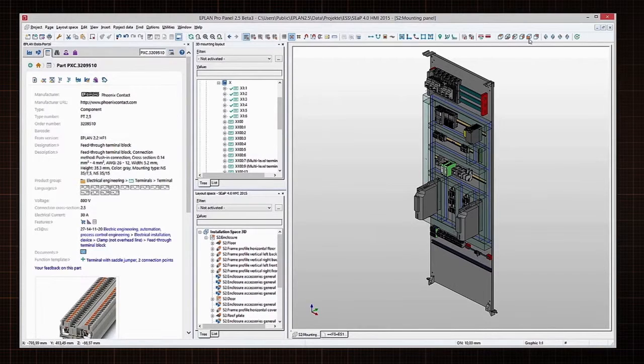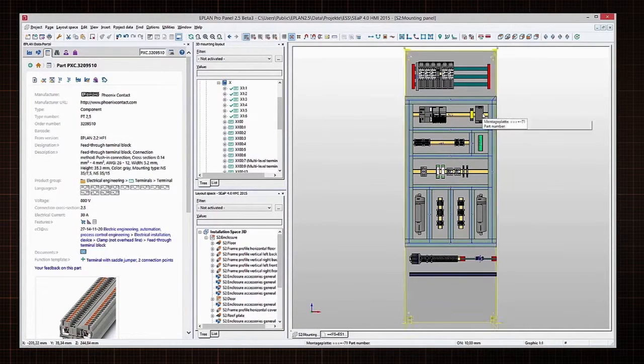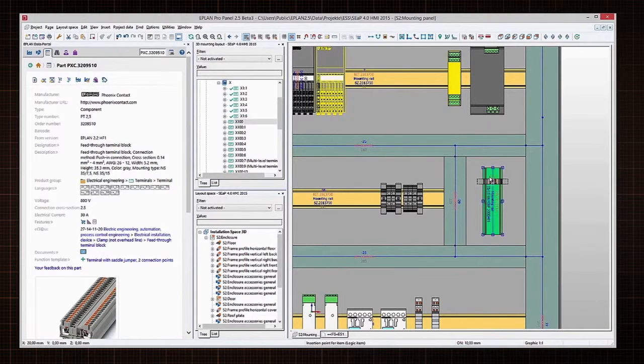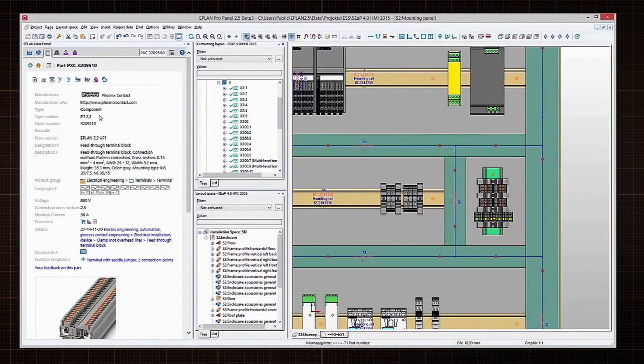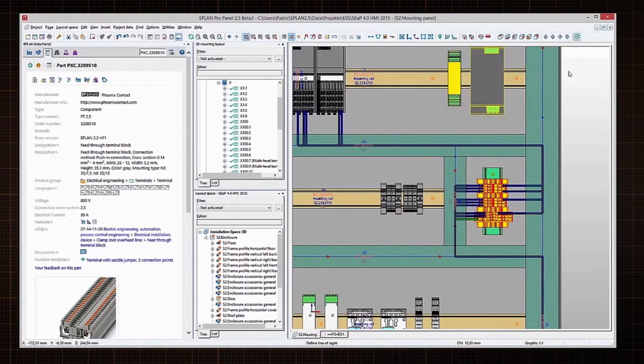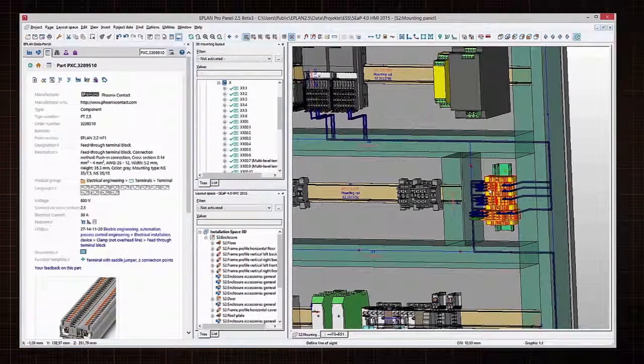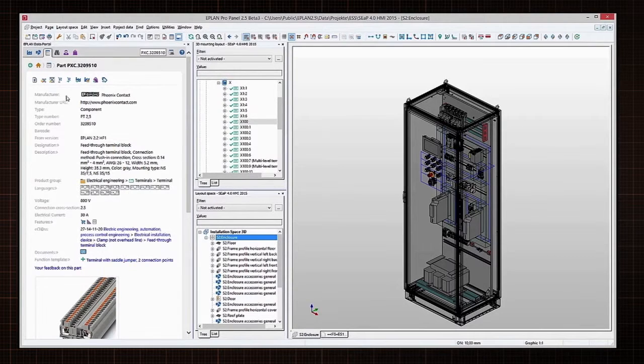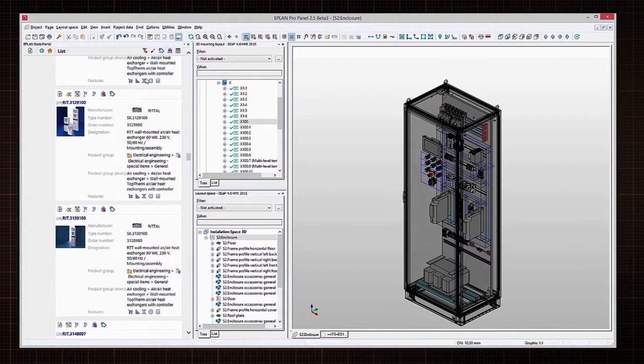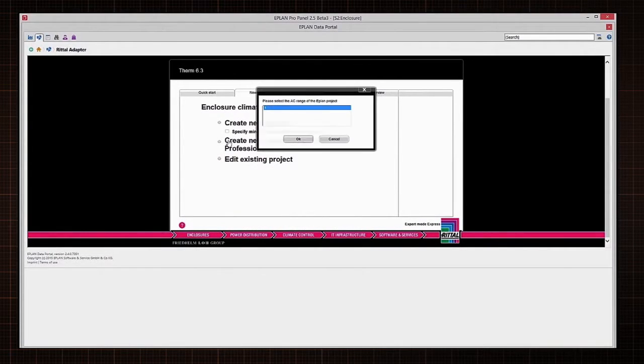The schematic diagram is then used as the basis for building a 3D model that incorporates all information required for downstream production processes. Moreover, this model contains all data needed for machining operations, for wiring and for creating pre-cut and pre-assembled cables. Defined machine interfaces are able to analyze and process this data and transfer it to existing manufacturing systems. Following the virtual assembly of components in the enclosure, the digital product data can be used to determine the total power dissipation of the control cabinet application. ePlan transfers this data on power dissipation plus key information on voltage, the enclosure location within the factory, interior and exterior temperatures and nearby media to Rittal Therm.